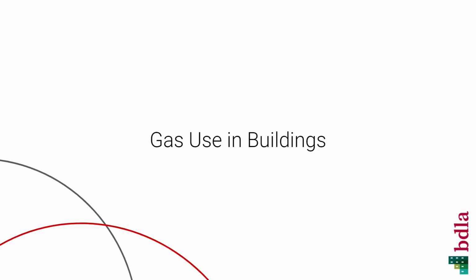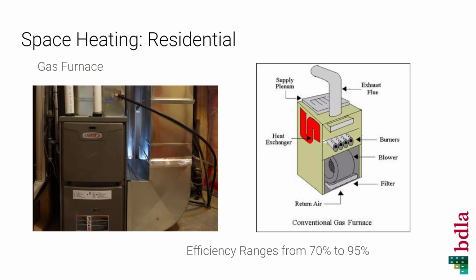So first of all, as a reminder, how is gas currently being used in our HVAC systems? This is a look at a typical residential gas furnace. A lot of houses in the US, especially in the Northeast, have these kinds of furnaces. It's using gas combustion to heat air, which is then distributed around the house. The efficiency can range and is particularly dependent on how old the equipment is, but somewhere in the neighborhood of 70 to 95%.